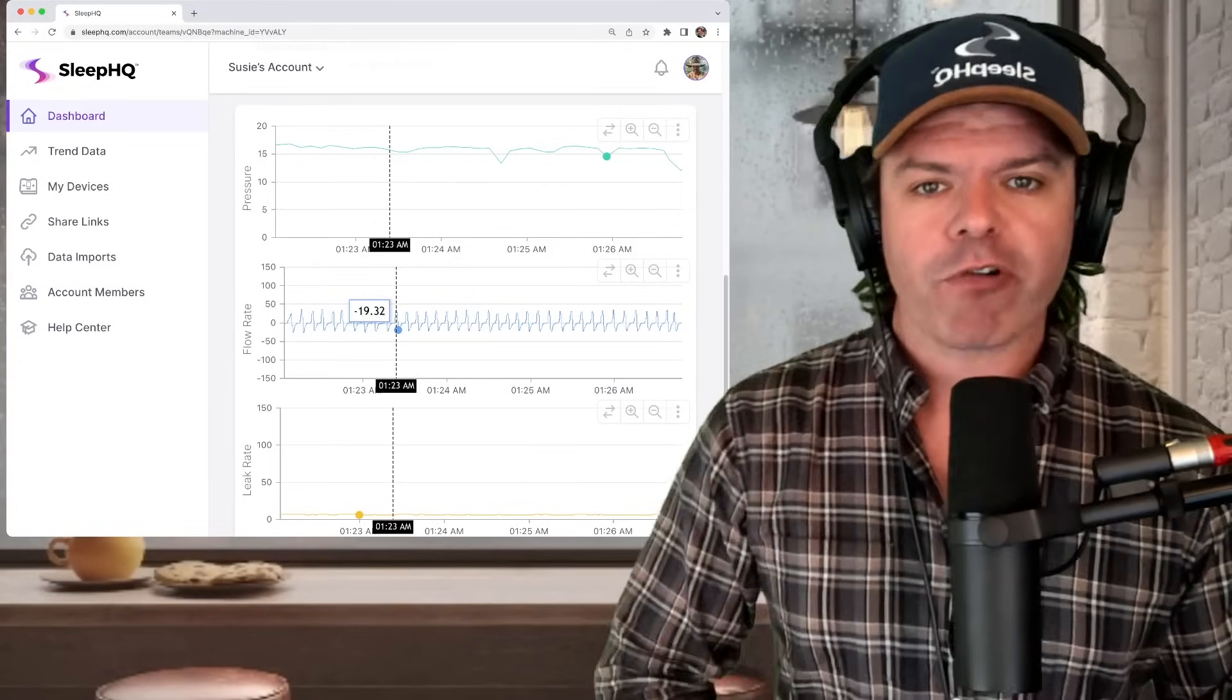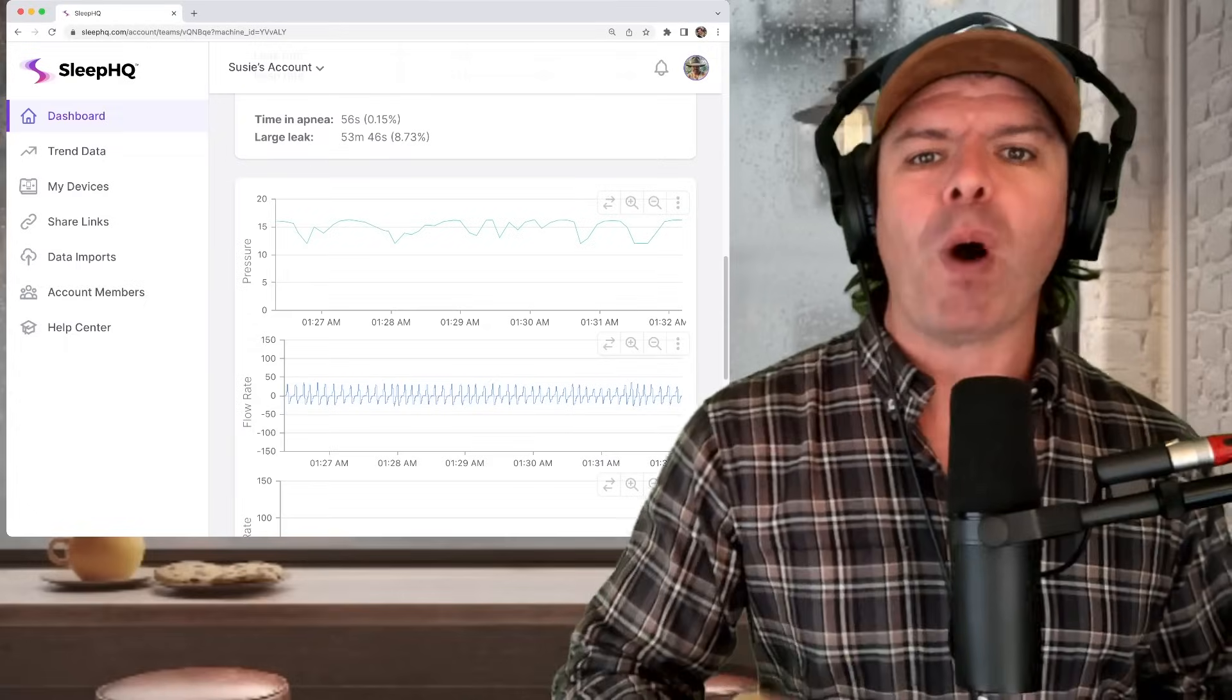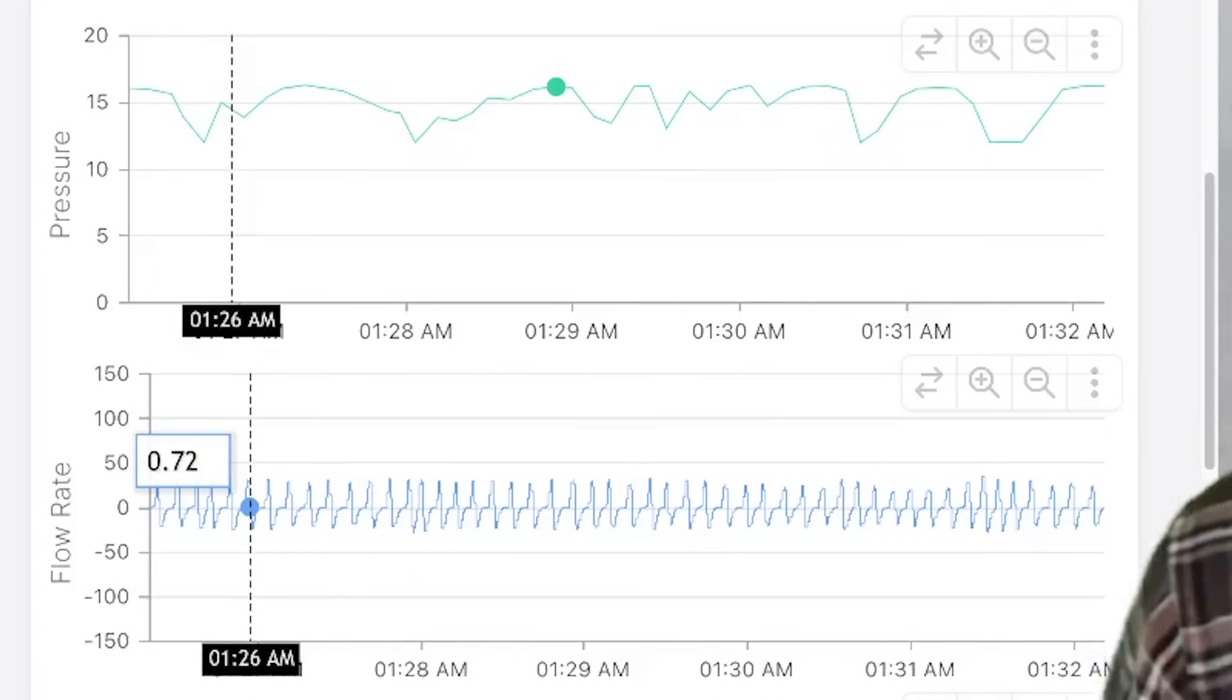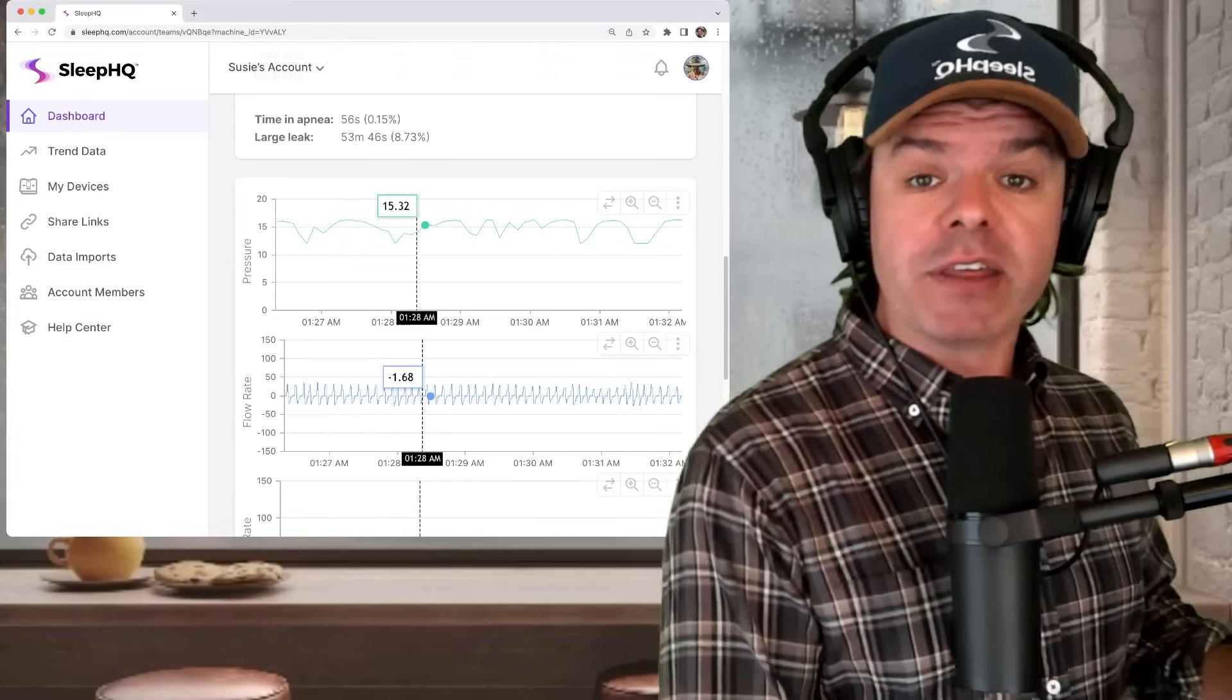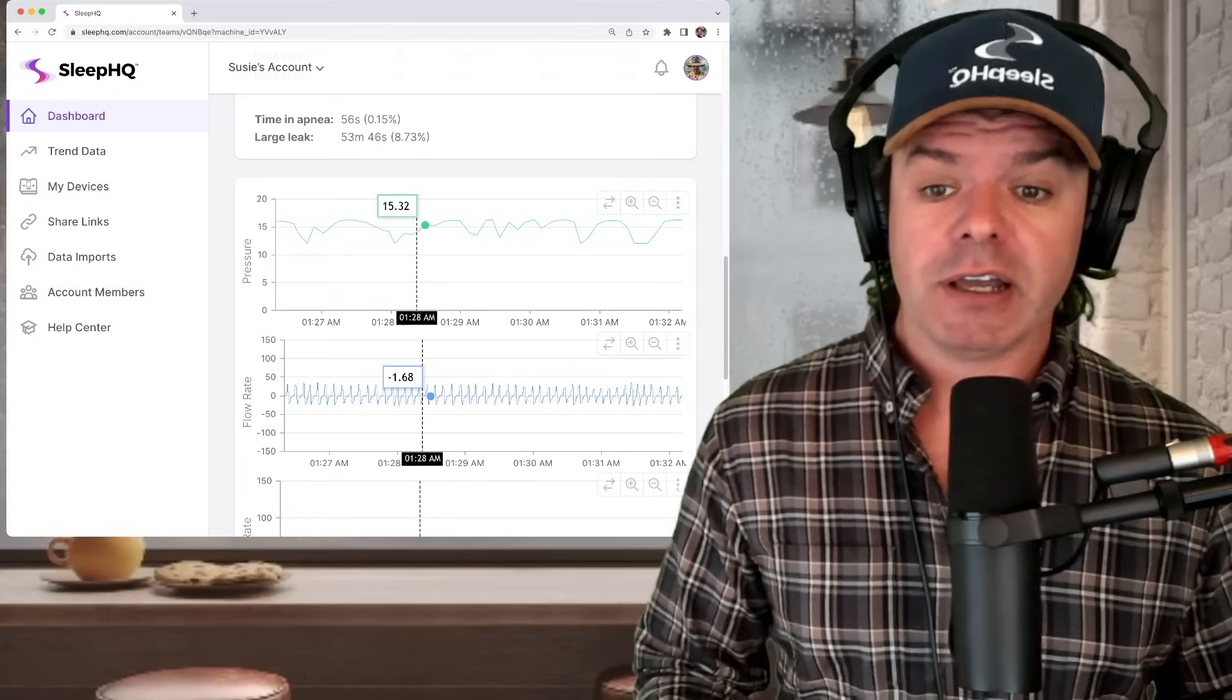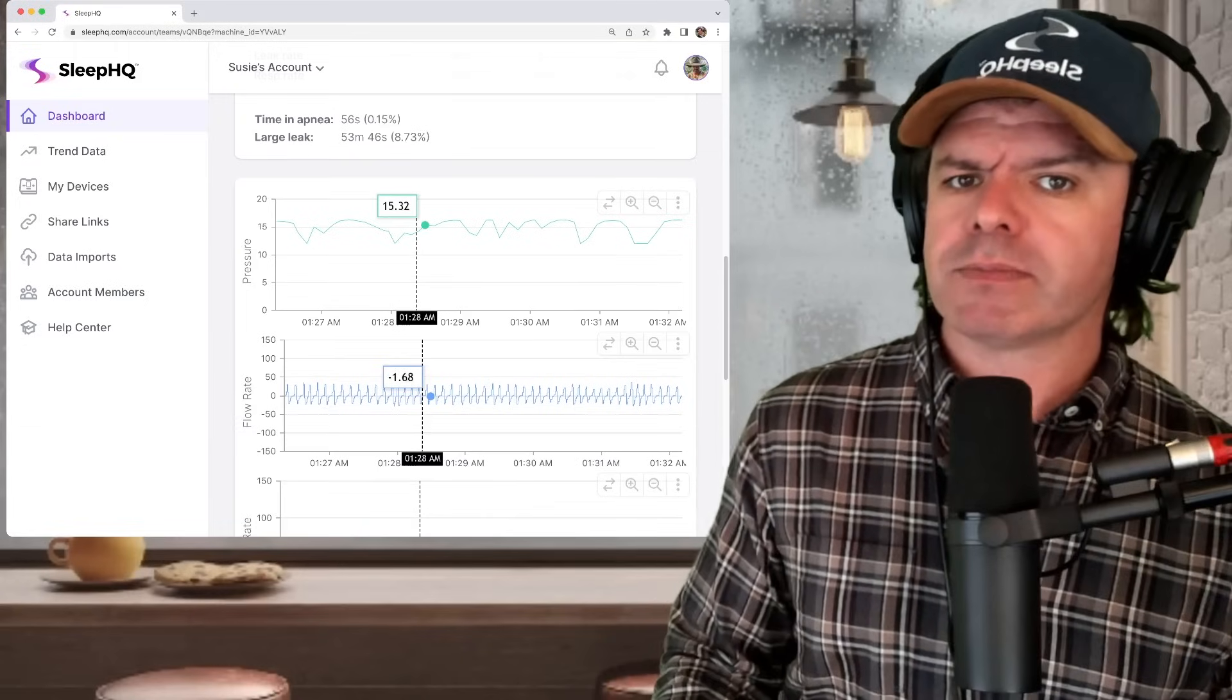Those of you with a keen eye might have spotted something on this page that doesn't look quite right. Can you see what it is? You have this wonderful, stable, regular breathing. But then up here on the pressure trace, it's all over the place. It's up, it's down, it's everywhere. Now, normally, if you have nice stable breathing, the pressure trace is also nice and stable because there's no need to change the pressure if your breathing looks good, right? So what's going on? Well, would you like to know how ASV works? Of course you would. I'm going to show you.